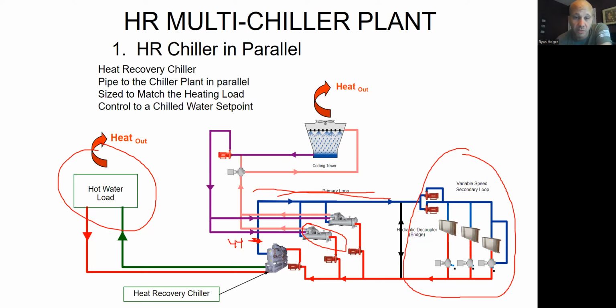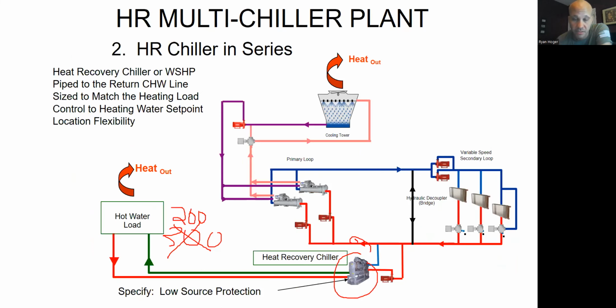So in this parallel arrangement, if this chiller needs to start staging down because this load is so low on the heating side, that means that somebody else has to come on and take care of this cooling. In this case, I'm always having someone else come on. This guy's always sending water to them. He's super small compared to these guys, so these guys barely even notice it. They'll ramp up slightly, but it's not like I have to turn another machine on.